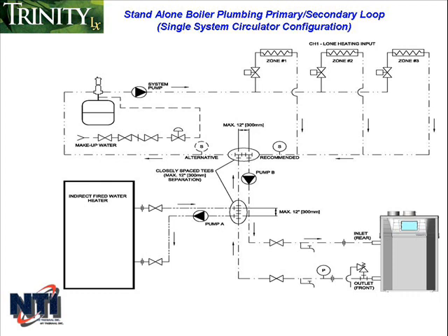Or you could choose the system temperature and place the factory supplied strap-on sensor out in the secondary so the boiler will be able to monitor that temperature. Choosing the system as the modulation sensor means the boiler will modulate itself in order to maintain the water temperature within the system at the target water temperature.